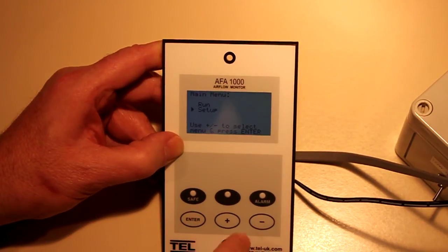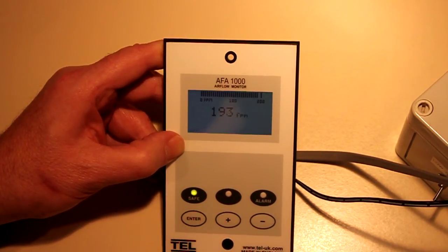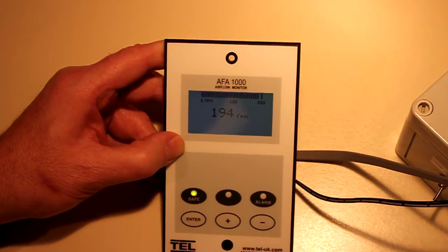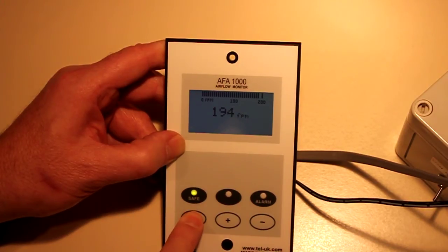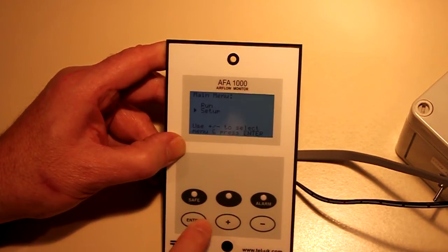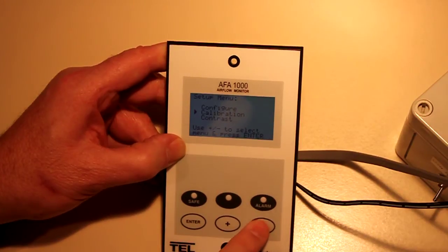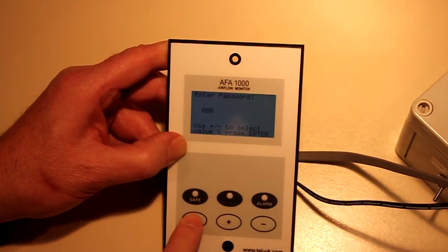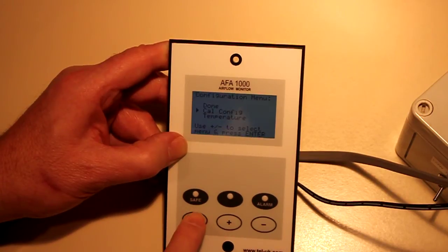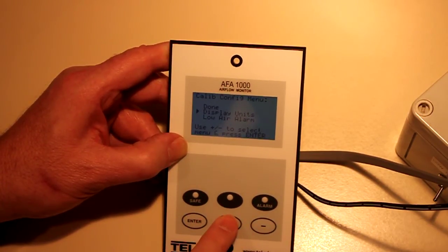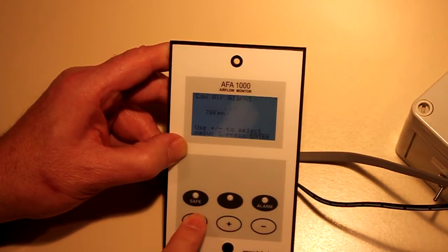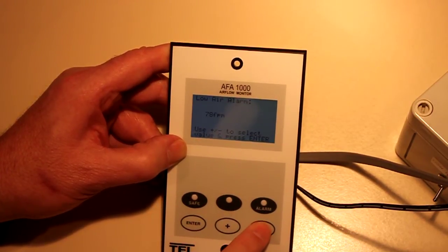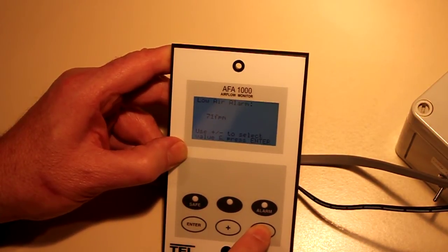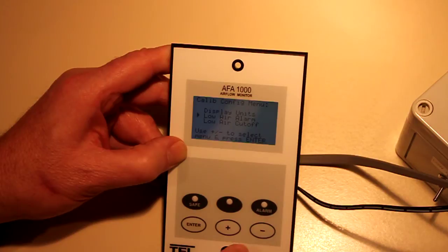After a successful calibration, choose Run, and the AFA 1000 will begin to show actual face velocities at any sash position. The low air alarm point is preset to 80 feet per minute. To change that value, press and hold the Enter button again to bring up the Run Setup menu. Choose Setup, Configure, and CalConfig. Use the plus or minus key to scroll to Low Air Alarm. Press Enter and use the plus or minus key to input a different alarm point. Then press Enter to accept the new value, then back to Done and Run.